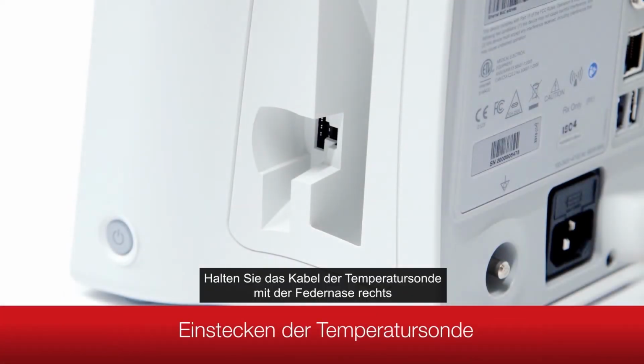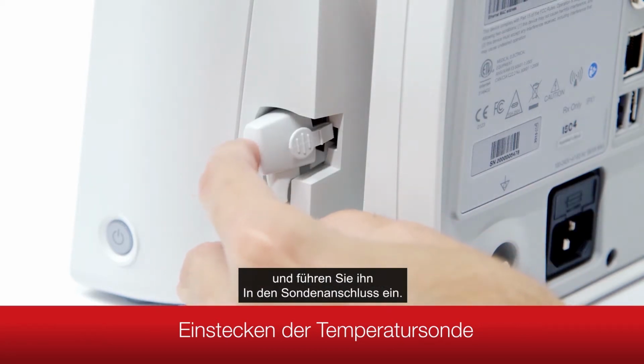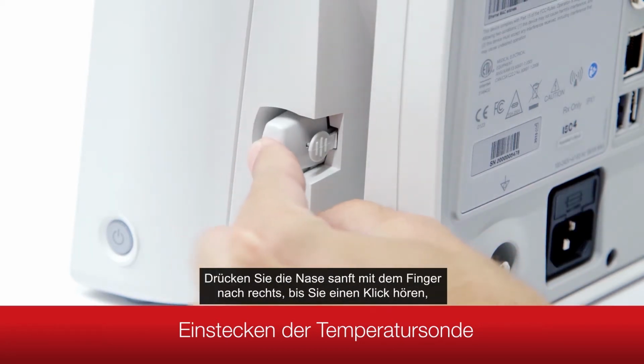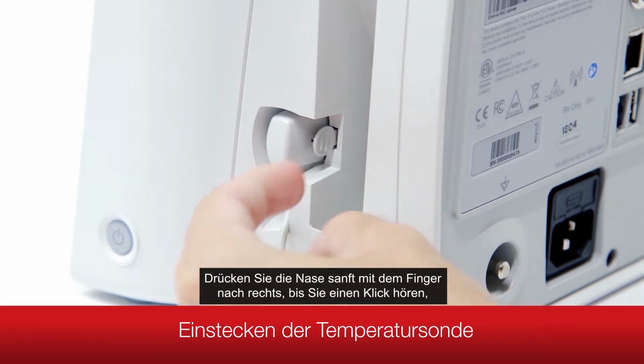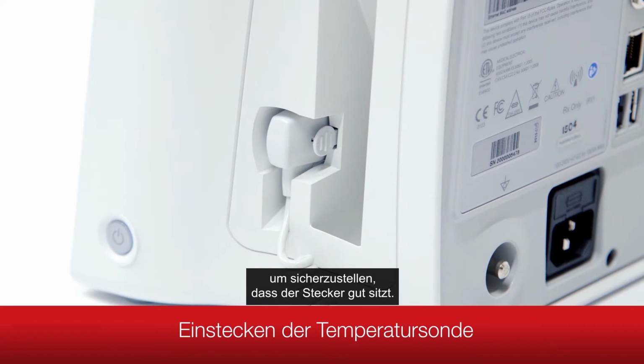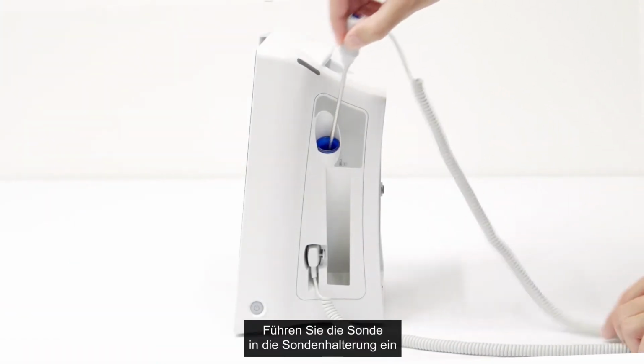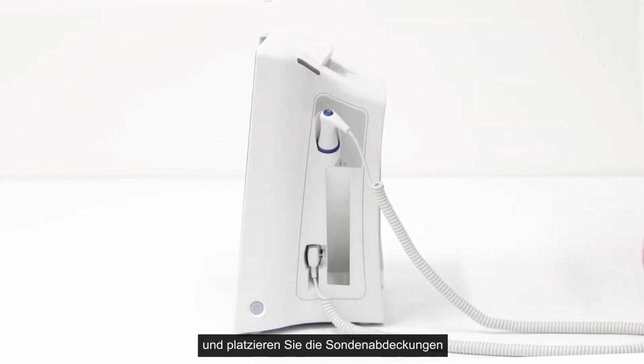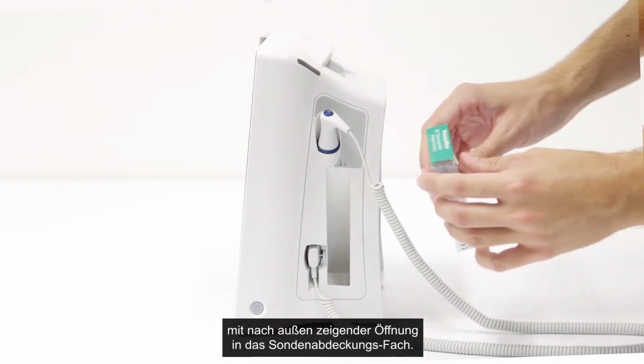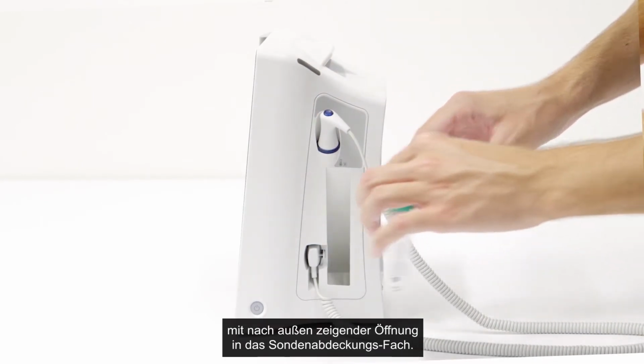Hold the temperature probe cable connector with the spring tab on the right and insert it into the probe port. Ensure that it is all the way in by gently pushing the tab to the right with your finger until you hear a click. Insert the probe into the probe well and place the probe covers with the opening facing outward into the probe covers holder.